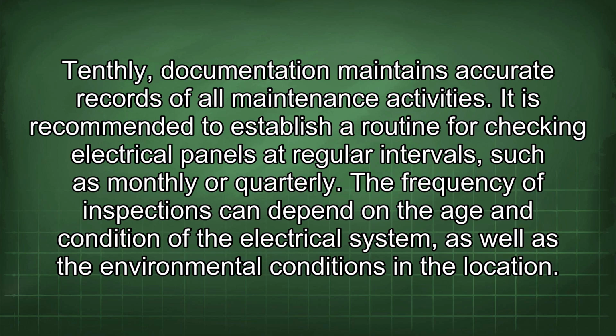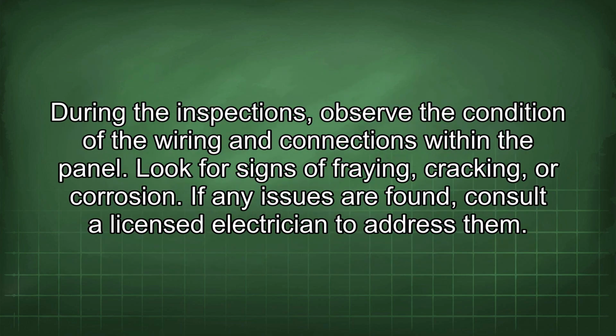It is recommended to establish a routine for checking electrical panels at regular intervals, such as monthly or quarterly. The frequency of inspections can depend on the age and condition of the electrical system, as well as the environmental conditions in the location. During the inspections, observe the condition of the wiring and connections within the panel. Look for signs of fraying, cracking, or corrosion. If any issues are found, consult a licensed electrician to address them.